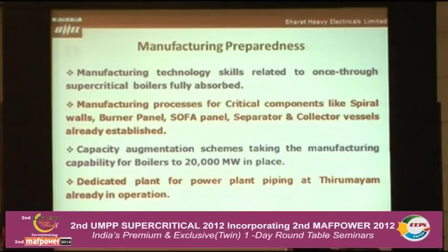And the manufacturing of this supercritical boiler, when compared to subcritical boilers, differs only in the evaporator system, because your fans, ESP and air heater do not matter whether it is subcritical or supercritical. Gas side performance is not at all affected. On the steam side, too, there is a change in the evaporator side alone.